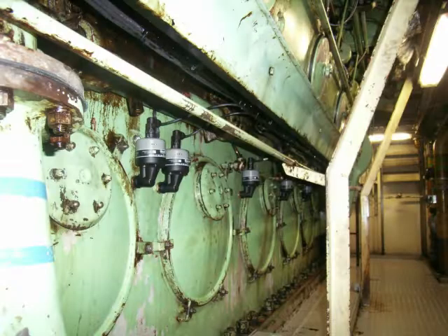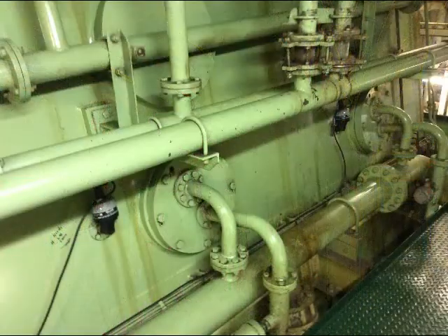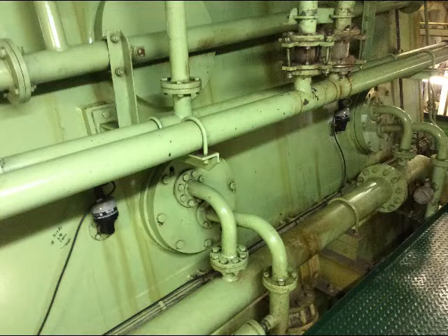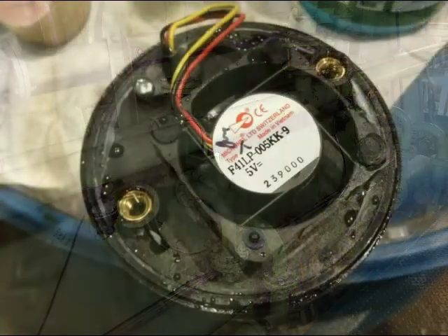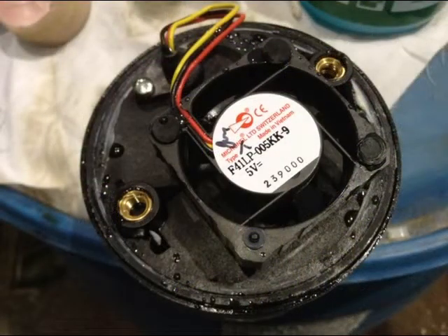Over time, oil can build up on the inside of the detector sample chamber. If allowed to continue, it could eventually prevent the detector detecting oil mist, and failing to give an alarm. To prevent this from occurring, the system monitors the level of oil contamination in each detector, and indicates a fault if the level of contamination becomes unacceptable. At this point, the detector sample chamber should be cleaned, to return it to normal operation.